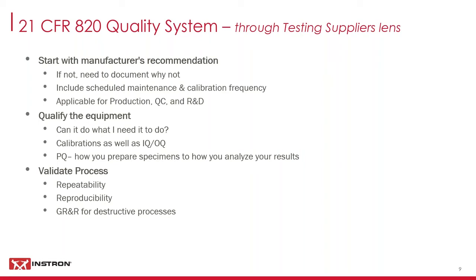So not only should you be documenting and following the process and procedures, you actually should be qualifying the equipment as well. And that includes having the actual calibration and IQOQ completed. Usually you as the device or drug manufacturer are handling the PQ portions, but material testing suppliers like Instron can even assist there and can save you a ton of time. So I think you should always keep that in consideration as you're going through the process. Lastly, once you have the process established, it's important to validate it. And that includes doing, as we say here, repeatability testing, reproducibility testing, and using different tools like GR&R, Gauge R&R, and other statistical processes. Make sure you're having these types of discussions up front with suppliers like us, and we can help you simplify processes and ensure that they're totally robust. We really truly can help quite a bit in this area.